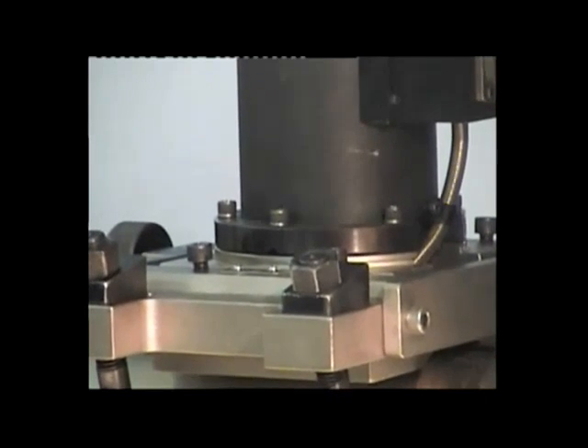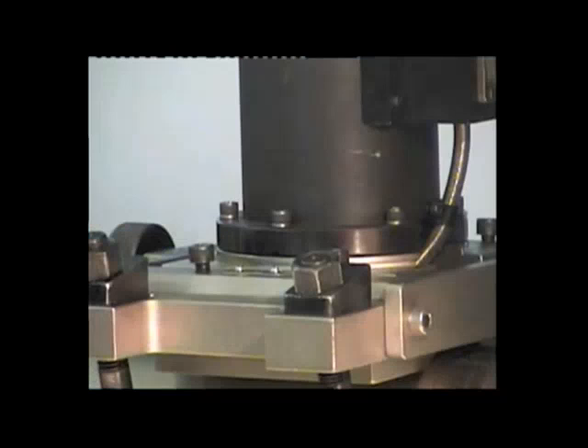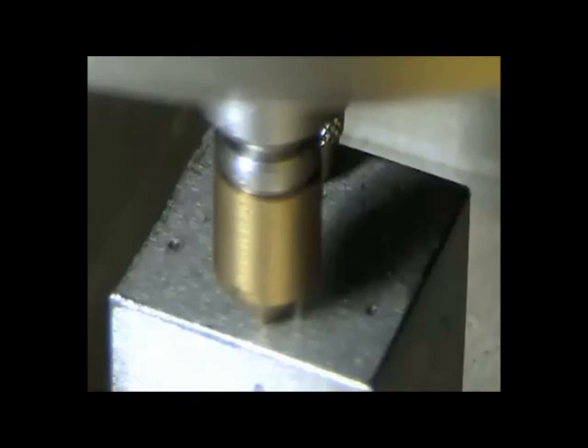This is main unit with fixture for placing small test specimen. Its weight is 12 kilograms only. Therefore it can be carried to site easily. In case of laboratory use the test specimen size may be 5 x 5 x 3 millimeters cube.